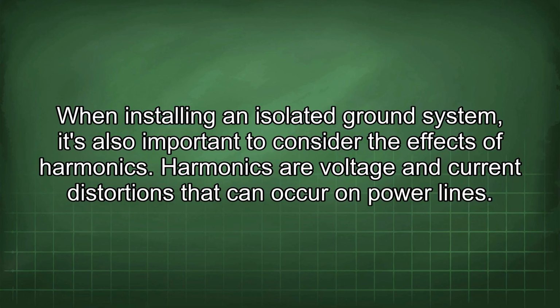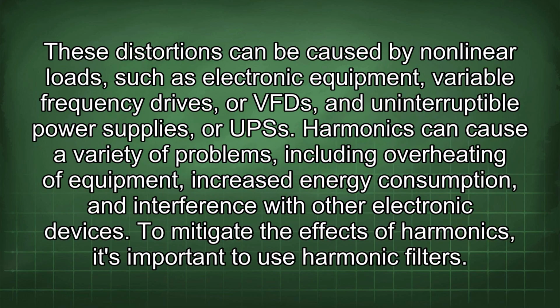Harmonics are voltage and current distortions that can occur on power lines. These distortions can be caused by nonlinear loads, such as electronic equipment, variable frequency drives, or VFDs, and uninterruptible power supplies, or UPSs. Harmonics can cause a variety of problems, including overheating of equipment, increased energy consumption, and interference with other electronic devices. To mitigate the effects of harmonics, it's important to use harmonic filters.